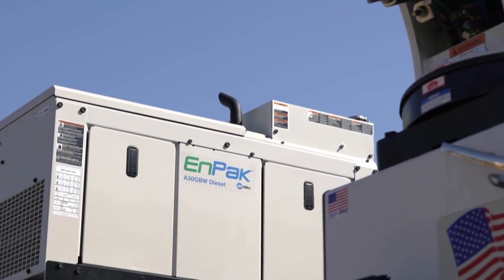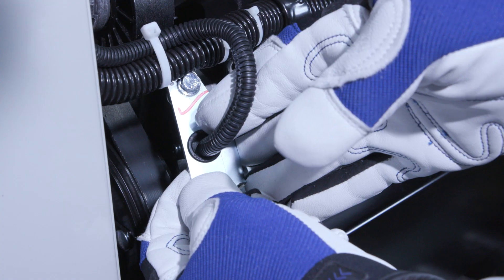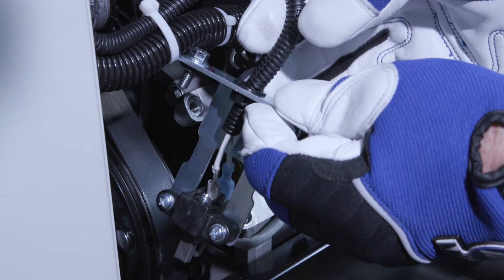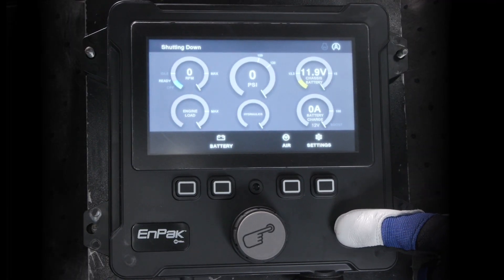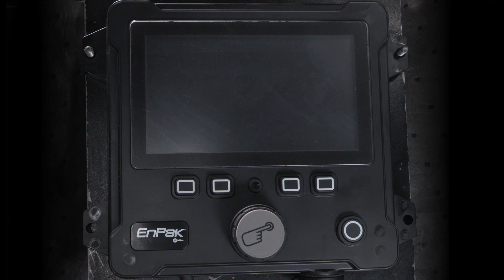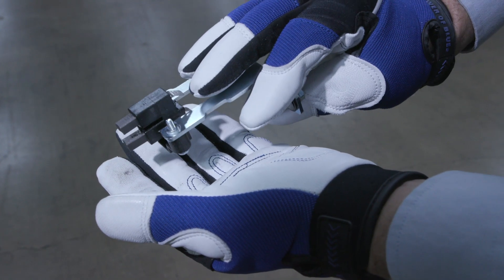Follow these tips for proper brush maintenance. Read and follow all labels and the owner's manual. Buy brushes from Miller to ensure proper quality and design. Always turn the EnPak engine off before changing brushes. When you change the brushes, inspect them to see how they're wearing. Uneven wear could indicate a problem.